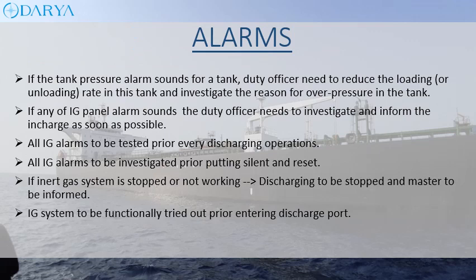If the tank pressure alarm sounds for a tank, the duty officer needs to reduce the loading or unloading rate in that tank and investigate the reason for over-pressure. If any IG panel alarm sounds, the duty officer needs to investigate and inform the officer in charge as soon as possible. All IG alarms are to be tested prior to every discharging operation and investigated prior to being silenced and reset. If the inert gas system is stopped or not working, discharging must be stopped and the master is to be informed. The IG system is to be functionally tried out prior to entering the discharge port.